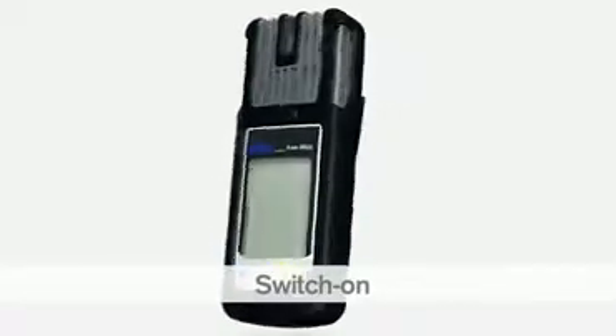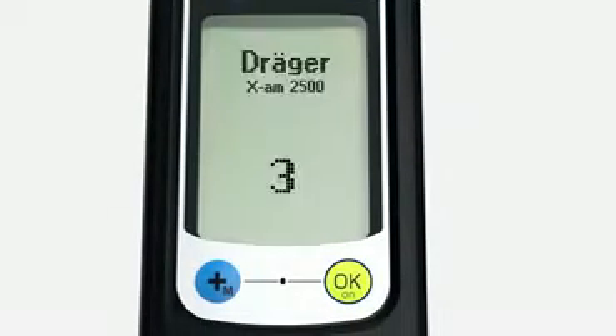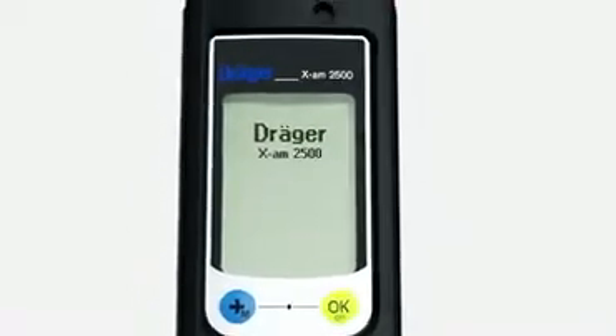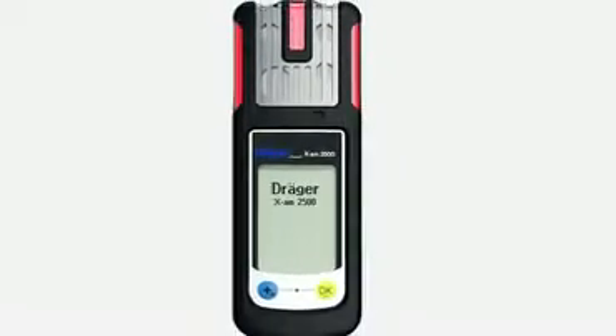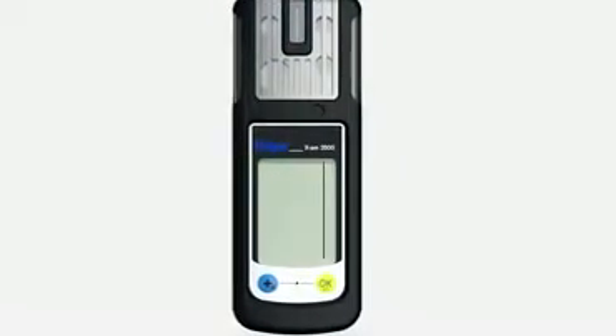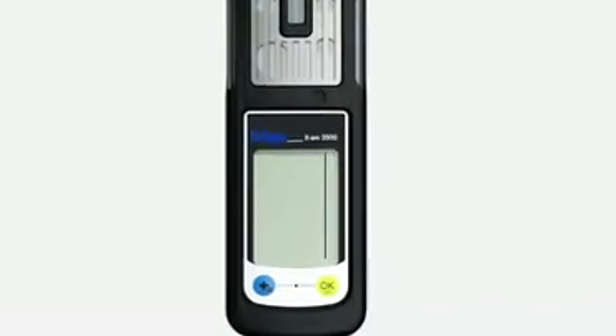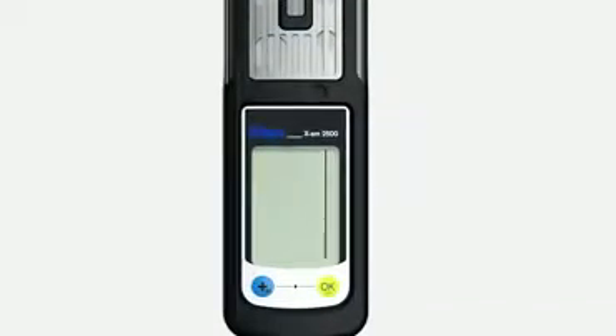To switch on the X-am 2500, press and hold the OK key for 3 seconds. A countdown is shown in the display. The LEDs flash and the vibration alarm vibrates to show that the device has been switched on. The instrument starts the boot sequence and performs an automatic self-test. The self-test screen shows the installed software version, the special symbols, the number of days until calibration is next due, the alarm thresholds, the TWA and STEL alarm thresholds.